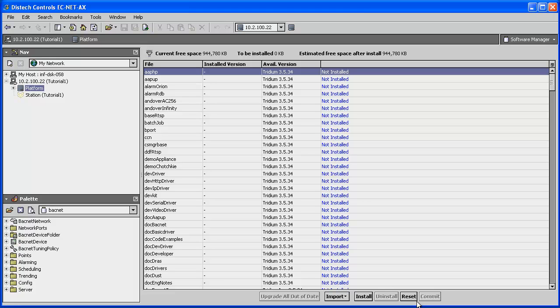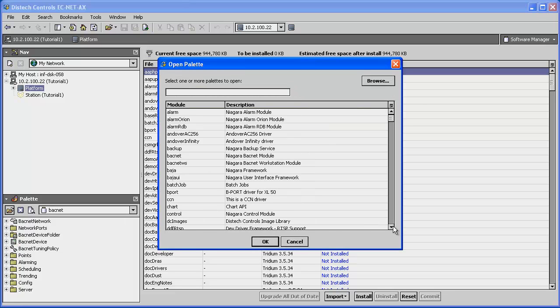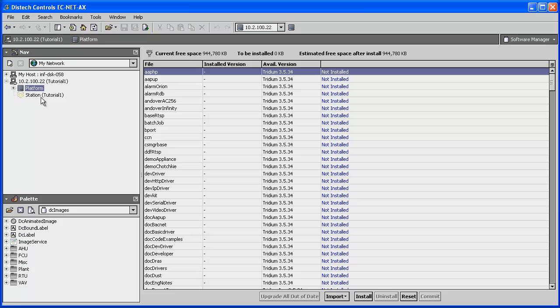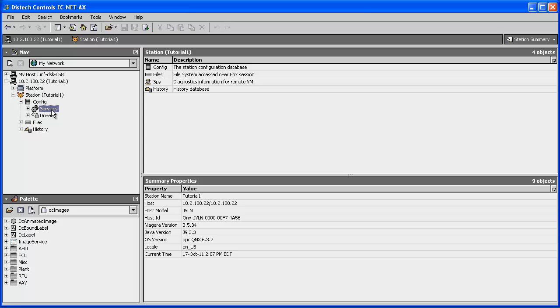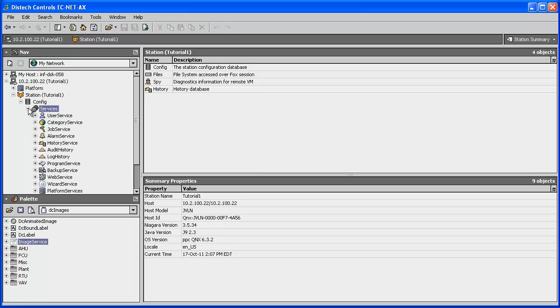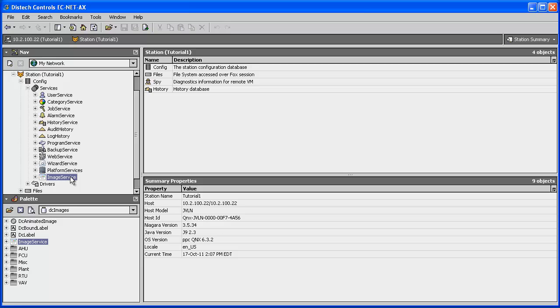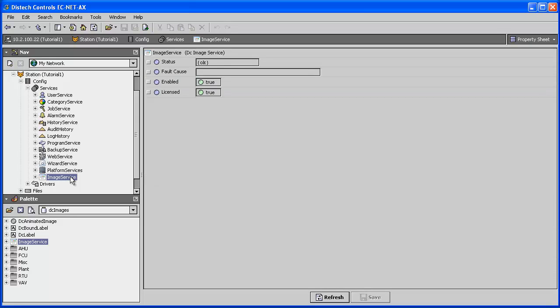Once the DC Images are installed, open up the DC Images palette. Click on Open Palette and select DC Images, then expand the Station folder. If you're not connected to a station, go ahead and do so. Then select the Image Service in the DC Images palette and drag and drop it into the Services folder of your station. If you expand the Services folder, you will notice the Image Service is now installed. The Image Service should already be licensed and enabled by default — Enabled is set to True and Licensed is set to True.